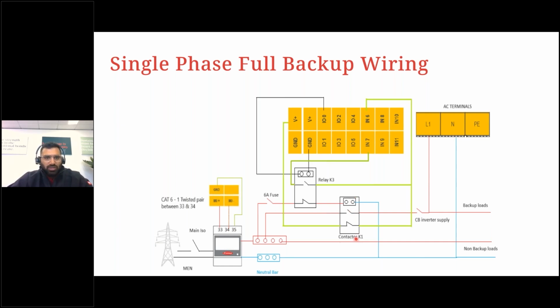So to achieve this break, we use a contactor. You can see the backup power loads are going through the normally open side of the contactor. The second part is what happens when the grid is suddenly reconnected. If the grid comes back again, we don't want this contactor to reconnect to the grid while the inverter is still running in backup. So what can we do here? We can use a relay, and we can pass the power supply of the contactor through the normally closed contact of this relay and keep this contactor open even when the grid has come back on. Now, this relay is actually power supplied by the inverter itself.